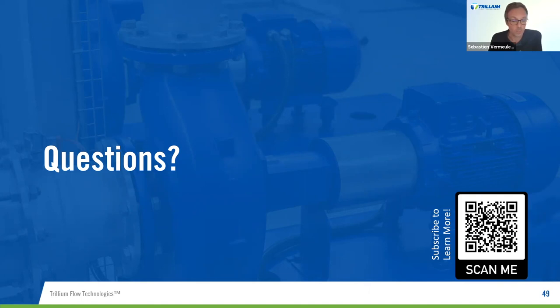Now, just to come back, we evolved separately, and what I mentioned, for example, regarding the pilot 76-78, full nozzle, semi nozzle, it's a big advantage to have the full nozzle. We are not the only one, but Emerson, for example, doesn't develop that. API has been developed in close partnership with Emerson, and that's the reason in API you only have semi nozzle pilot. But definitely, full nozzle is a big advantage because we promote on spring loaded type the full nozzle. And why should it not be the same for pilot?